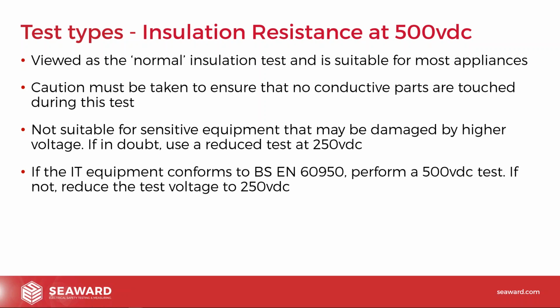I've been to organisations where they've had surge protected extension leads and they've actually failed them and chucked them away because they failed the insulation resistance test when actually they were doing their job. They were surge protected. And if they'd been tested at 250 volts, they'd have read absolutely fine. So just be careful of that. If you have got any surge protected equipment as well, you will get low insulation resistance readings at a 500 volt test because the surge protection is actually doing its job. And it is easy to mistake that for a fail if you're not careful.